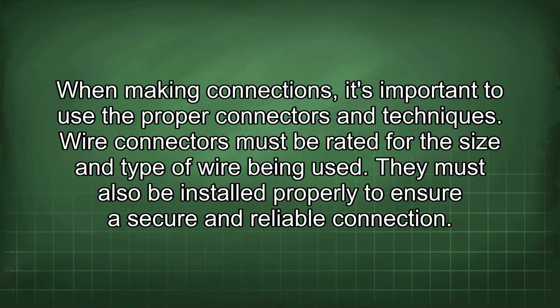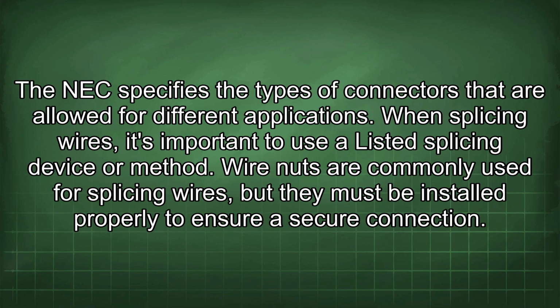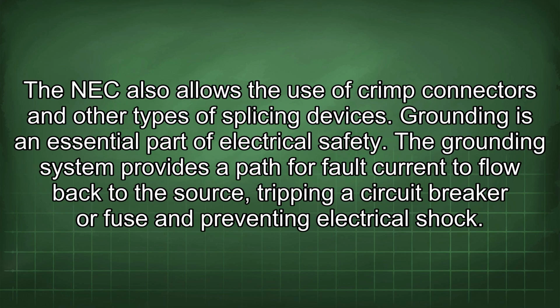When making connections, it's important to use the proper connectors and techniques. Wire connectors must be rated for the size and type of wire being used. They must also be installed properly to ensure a secure and reliable connection. The NEC specifies the types of connectors that are allowed for different applications. When splicing wires, it's important to use a listed splicing device or method. Wire nuts are commonly used for splicing wires, but they must be installed properly to ensure a secure connection. The NEC also allows the use of crimp connectors and other types of splicing devices.